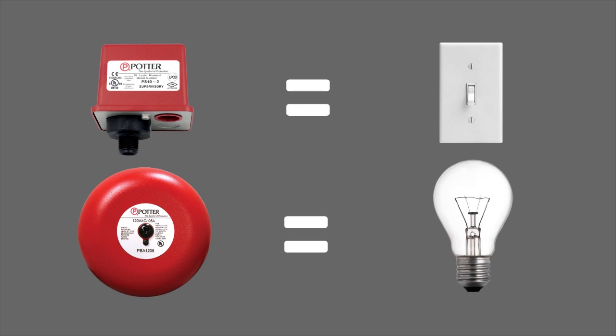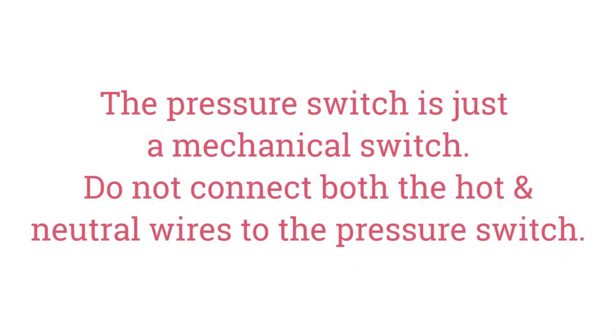The hot wire through the normally open contacts of the pressure switch out to the bell. The neutral wire does not connect to the pressure switch at all. The neutral wire goes from the service panel straight to the white wire of the bell.